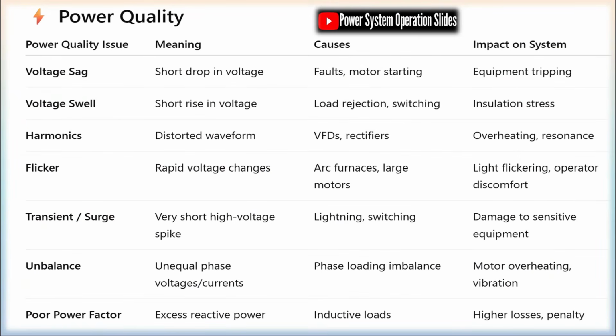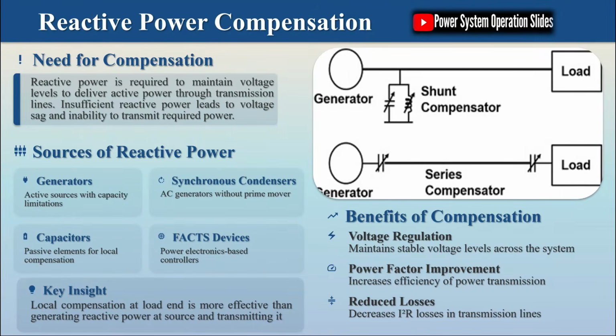The configuration of an SVC generally includes a fixed capacitor bank, a thyristor-controlled reactor, and a control system that monitors system voltage and adjusts the reactive power output accordingly. The control system typically uses a voltage regulator that compares the measured system voltage with a reference value and generates a control signal to adjust the firing angle of the thyristors in the TCR. This adjustment changes the effective reactance of the TCR, thereby controlling the reactive power exchange between the SVC and the power system.